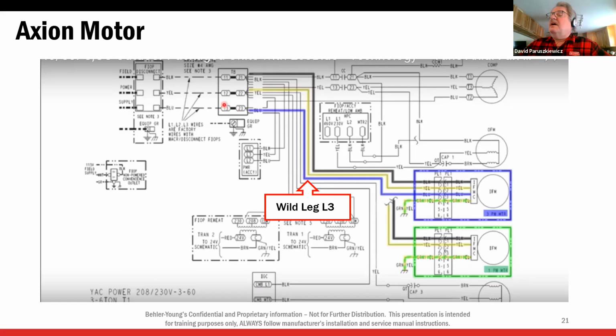So wild leg. I want you guys to make a note of this. Now, is everybody familiar with a wild leg? When we're dealing with 3-phase, sometimes we'll have one leg that's 208. It's called a wild leg. So two to ground is 208. If you got all 115 or 112 or 119, whatever, we don't have a wild leg. But if I have that wild leg, it has to go on L3. If you're dealing with a Bryant rooftop or a Carrier rooftop unit for that matter, if you have a wild leg, it has to go on L3. All right, it's going to be a test on that one later.